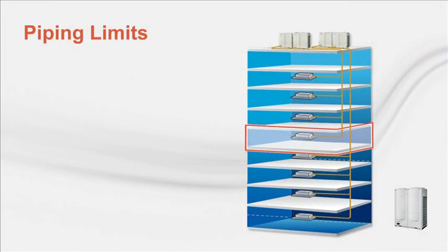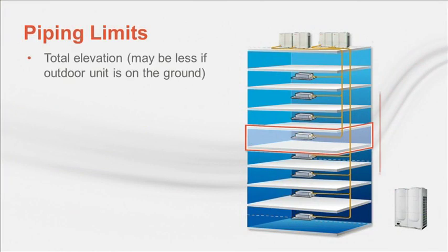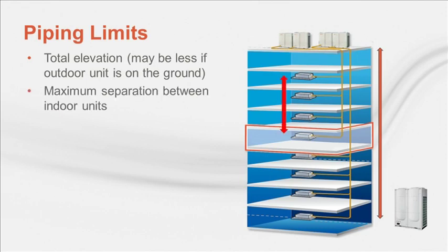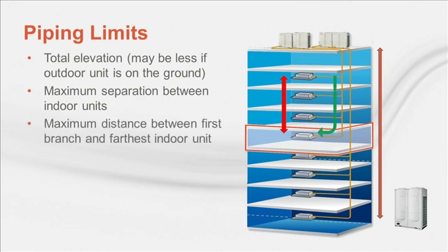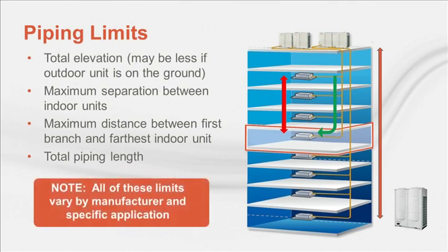Each manufacturer defines maximum limits for the requirements of refrigerant piping. The total elevation limit is the maximum vertical distance between outdoor unit and the furthest indoor unit. Sometimes this can be further limited if the outdoor unit is installed on the ground and needs to pump liquid refrigerant upwards. There is also a maximum separation distance between indoor units on a single circuit. And there's a maximum separation between the first branch and the furthest of the indoor units. And the sum total pipe length of an individual VRF refrigerant circuit is limited to 3,000 feet, depending on the manufacturer. That's a lot of pipe.